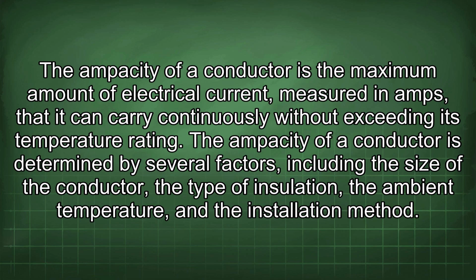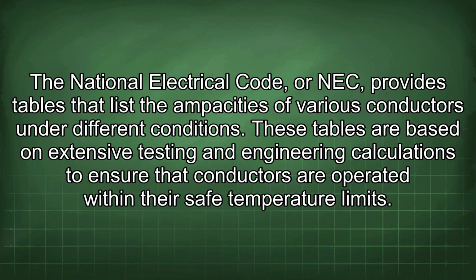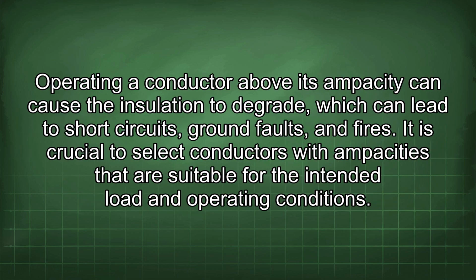The ampacity of a conductor is determined by several factors, including the size of the conductor, the type of insulation, the ambient temperature, and the installation method. The NEC provides tables that list the ampacities of various conductors under different conditions. These tables are based on extensive testing and engineering calculations to ensure that conductors are operated within their safe temperature limits. Operating a conductor above its ampacity can cause the insulation to degrade, which can lead to short circuits, ground faults, and fires. It is crucial to select conductors with ampacities that are suitable for the intended load and operating conditions.